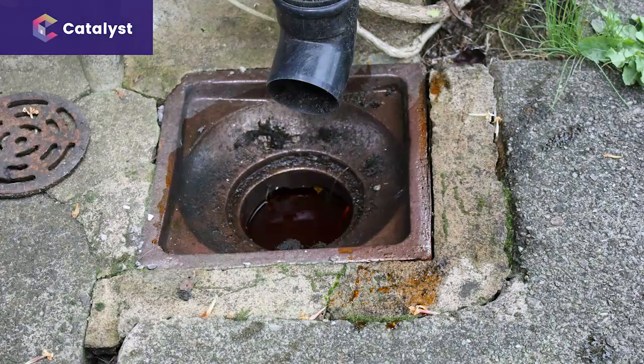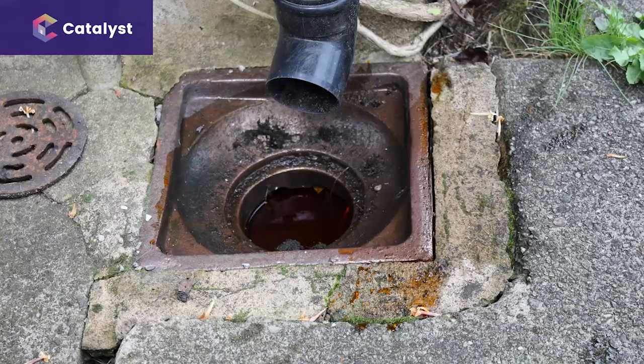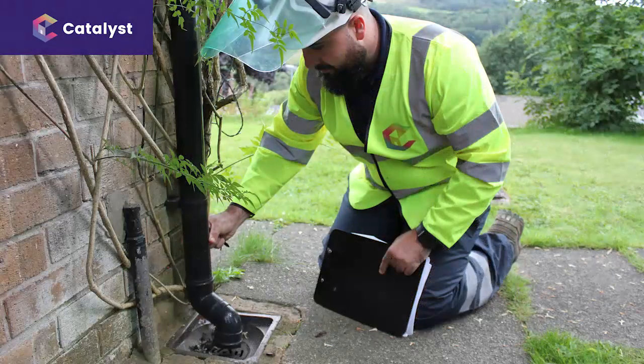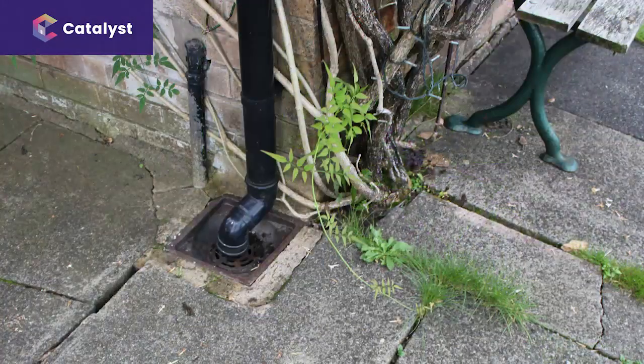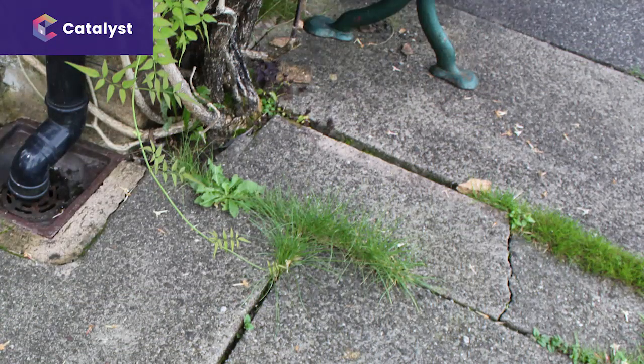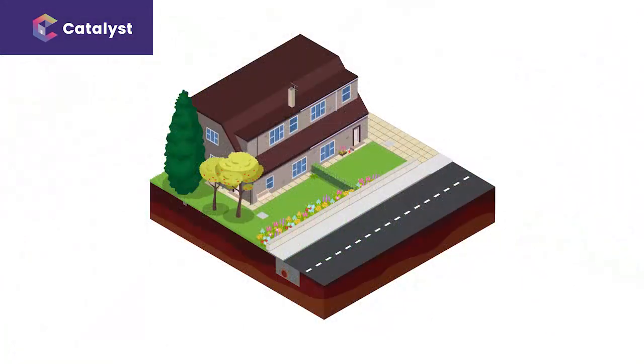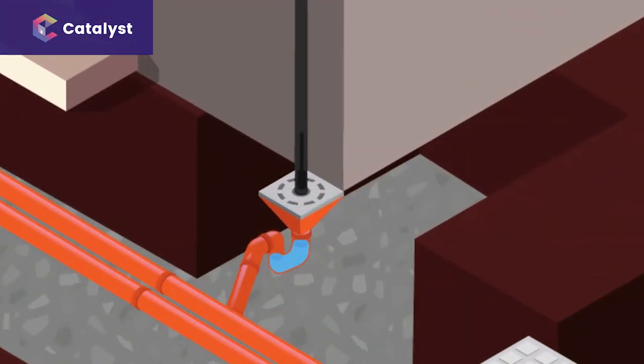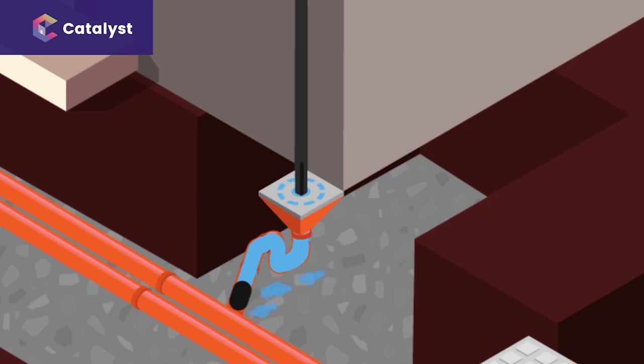The importance of water testing to check for leaks from sewer pipes is often overlooked. If soil testing or a visual inspection indicates that the ground around a drain is unusually soft, a low pressure water test should be considered. This is done by inflating an airbag in the section of pipe you want to check. You will need access to insert the airbag downstream and a visual on the water level upstream.